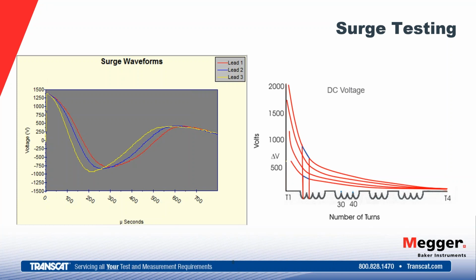So this sets us up to see if there's weak turn-to-turn insulation. And if we see weak turn insulation, then we're going to see that waveform jump. It'll shift to the left for us. And that's our sign that we've got a turn-to-turn weakness, or a copper-to-copper weakness, in our windings.